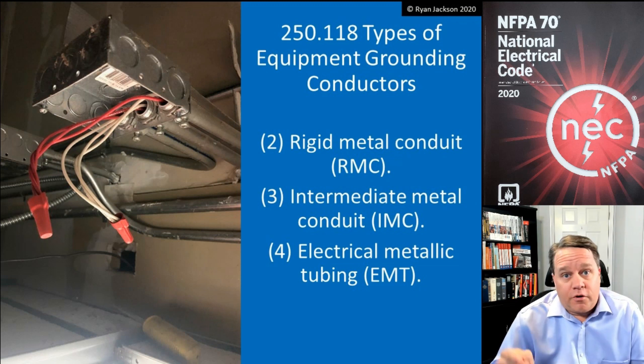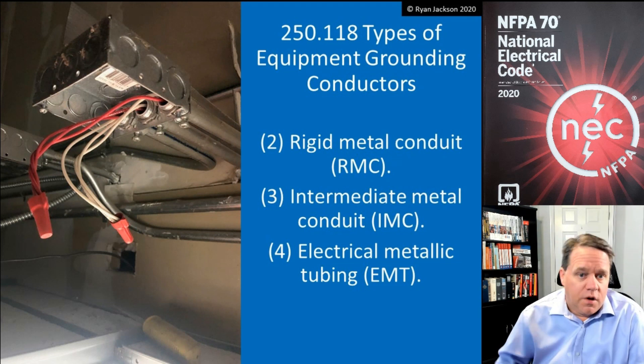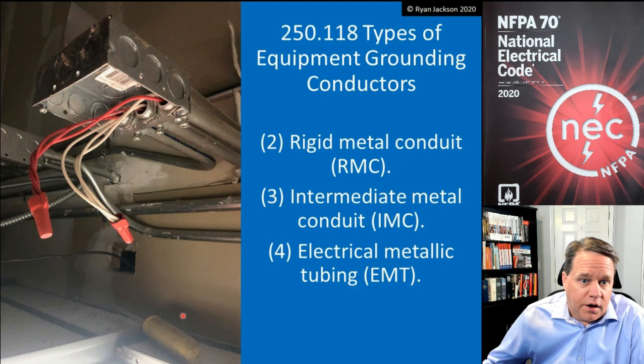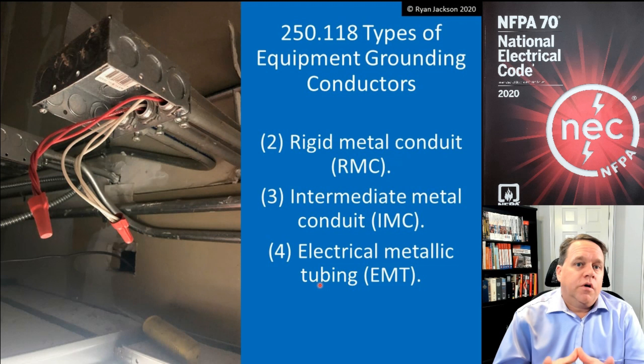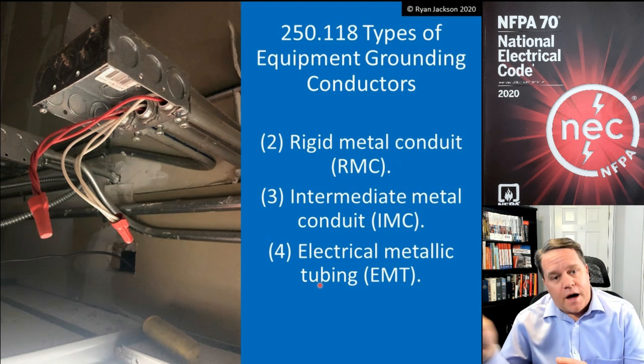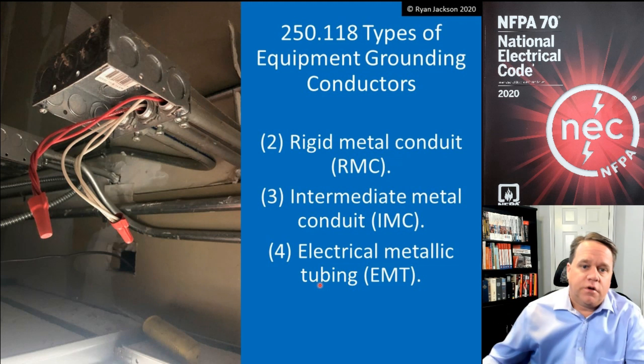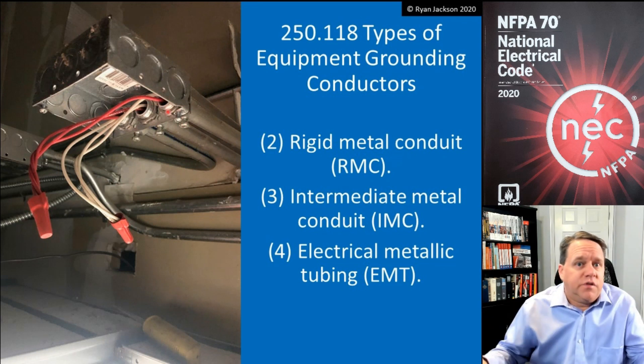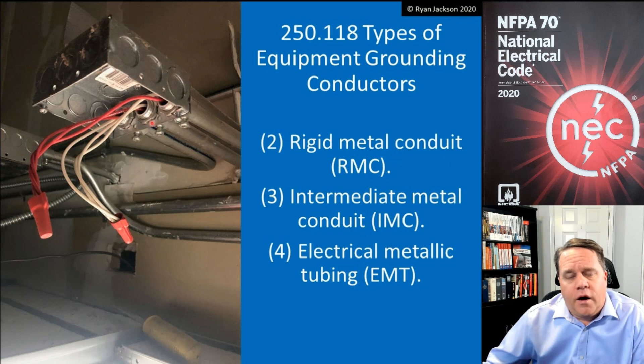We can use rigid metal conduit, intermediate metal conduit, or EMT. Here in the photograph we're using EMT as the equipment grounding conductor — that EMT bonds the normally non-current-carrying metal parts of the equipment back to the source. If you get continuity between the raceway and the box, it has connected the two together. So we don't necessarily have to have a green wire inside our raceway system — we can use the raceway itself as the equipment ground.